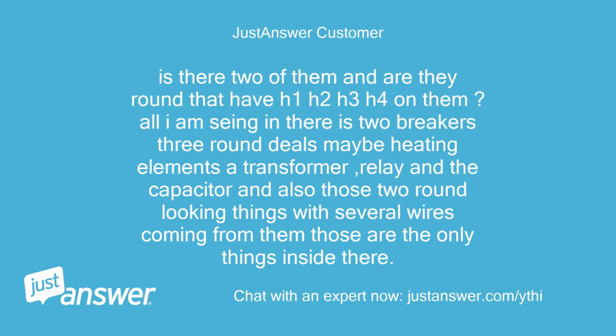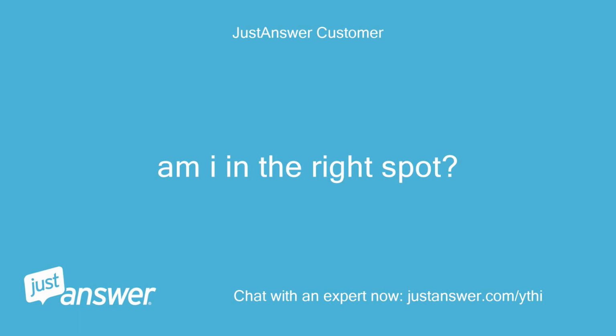Are there 2 of them, and are they round, with H1, H2, H3, H4 on them? All I am seeing in there is 2 breakers, 3 round deals, maybe heating elements, a transformer, relay and the capacitor, and also those 2 round looking things with several wires coming from them. Those are the only things inside there. Am I in the right spot?